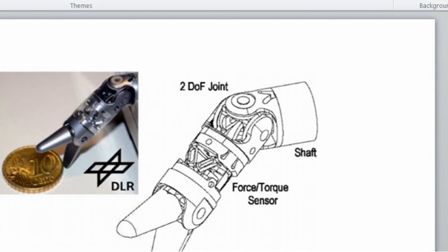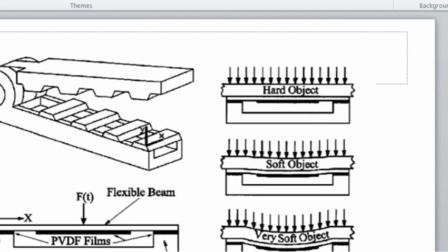The entire tactile array sensor was placed on a handheld laparoscopic palpation instrument, allowing the surgeons to press the sensor against the surface area of interest, with specially designed electronics and computer-based signal processing systems. Various forms of delicate palpation information, such as variations in pulsatile pressure in arteries, and stiffness and textures of soft tissues, could be read out and conveyed to the surgeon by either a visual or an intuitive tactile display.